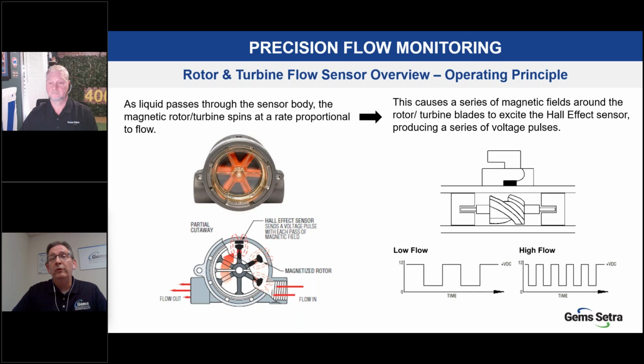So as I mentioned, the rotor flow and turbine products, the operating principles are identical. It's the packaging and how the turbine or rotor is situated in the body. On the left-hand side, we see the rotor flow, and down the bottom, you'll see the magnetized rotor. Each one of those vanes is magnetized, and as it spins, the sensor itself has a Hall effect sensor. As each magnet passes, that Hall effect sensor identifies that, oh, magnet there, not there, not there, there, not there, and is able to turn that into a proportional DC, a continuous pulse DC output.